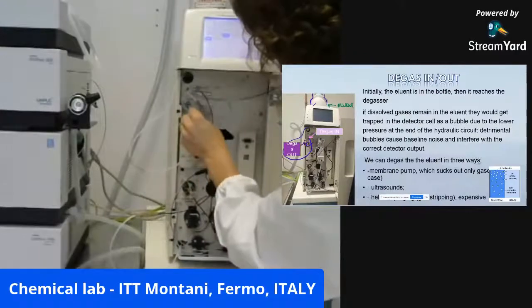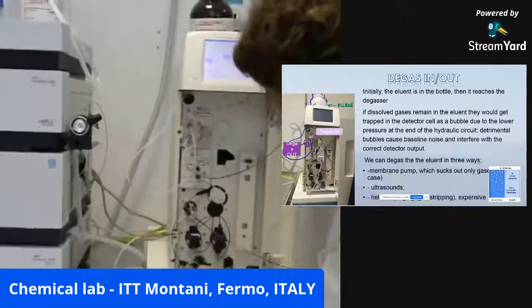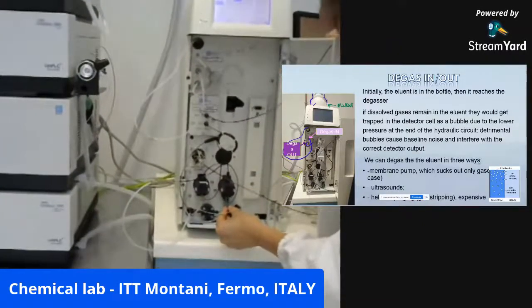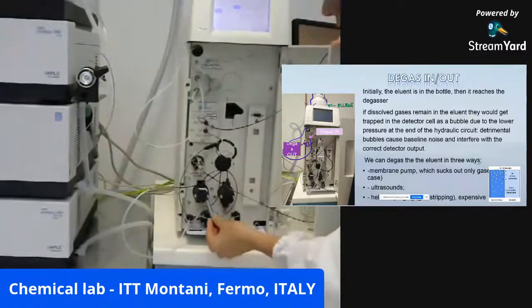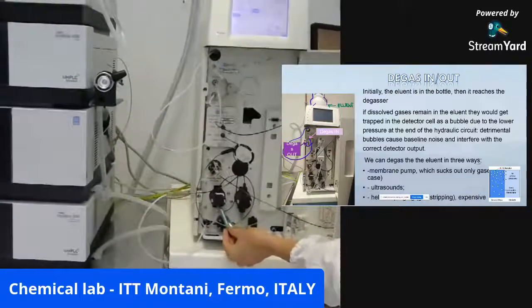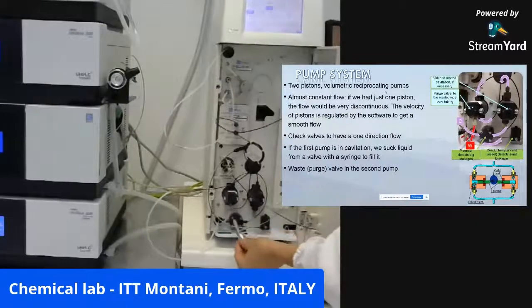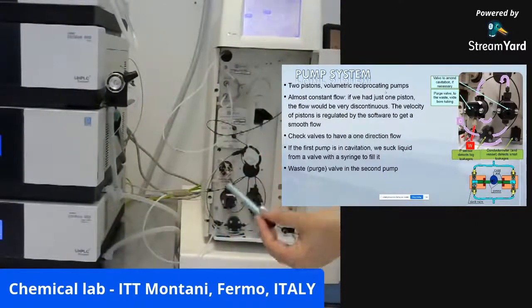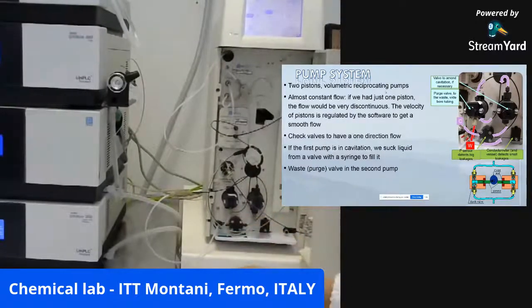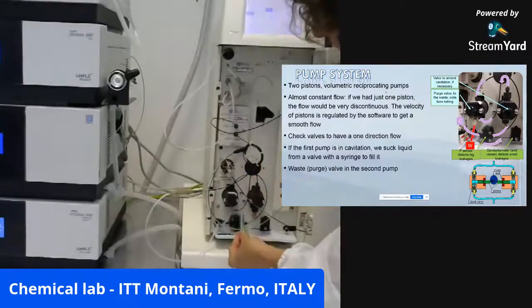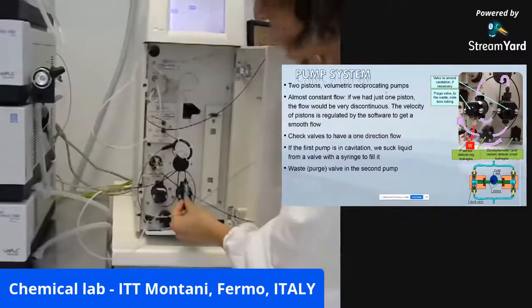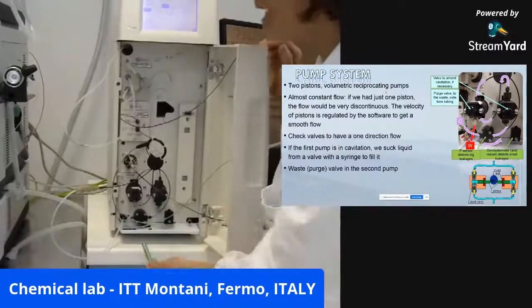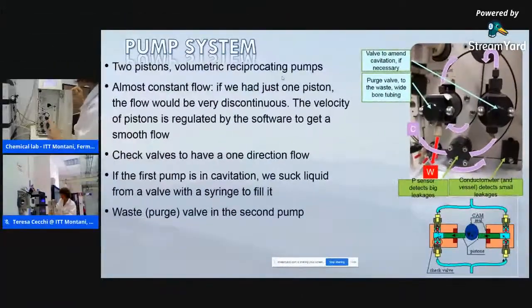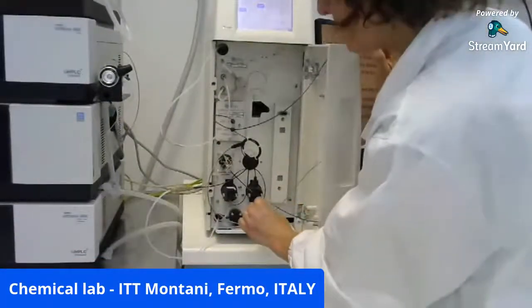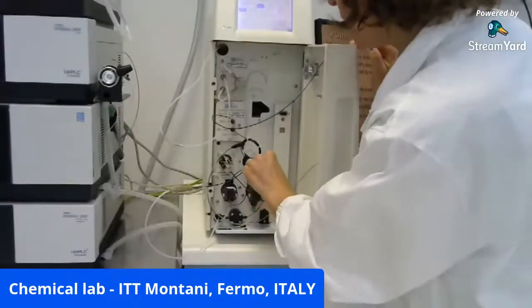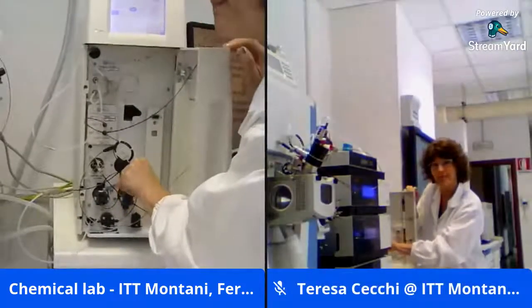After the degasser, you can follow here the circuit, the tubing, which enters the pump system. We have two piston pumps. They are reciprocating volumetric pumps. We have two pumps because we would like to deliver a flow as smooth as possible, but we will see that we also need a dampener later. Anyhow, the liquid enters the first head of the pump, and here you see there's a valve, because if the pump is in cavitation, we have to suck the liquid from here to amend the problem from here. From the first pump head, we go here and here to the second pump head.